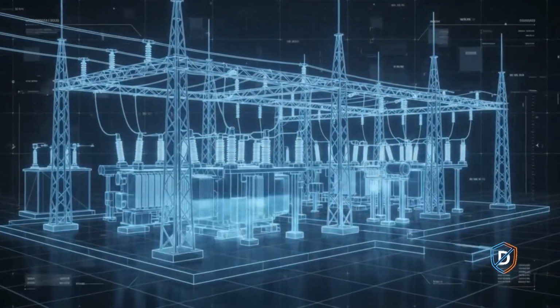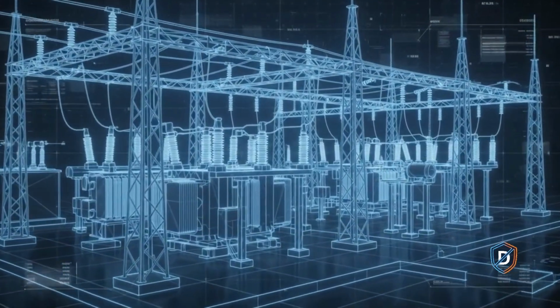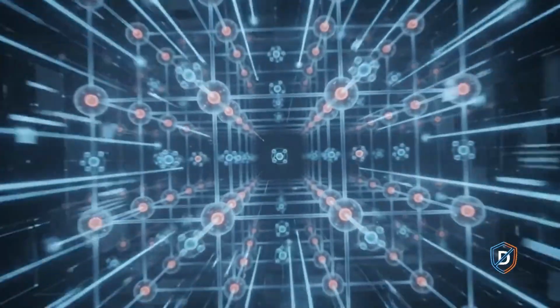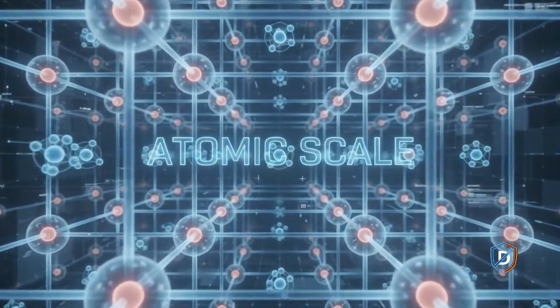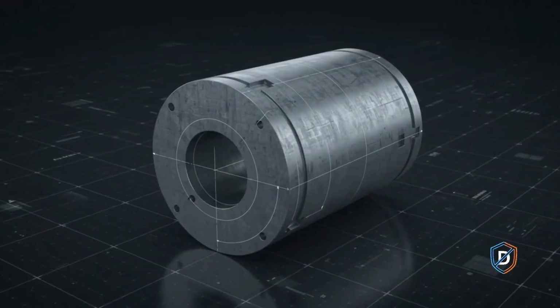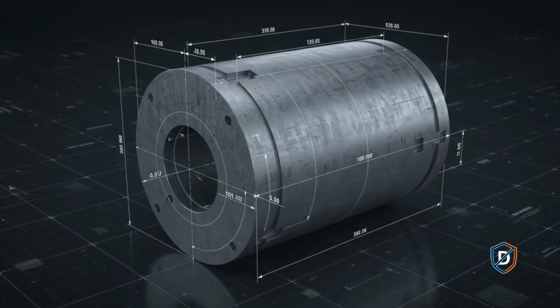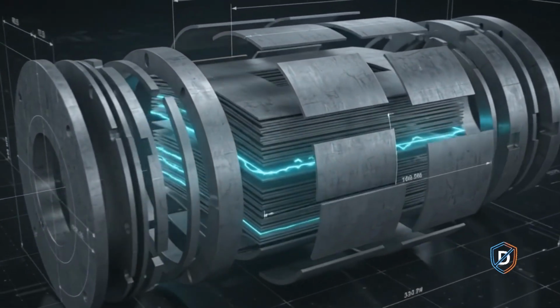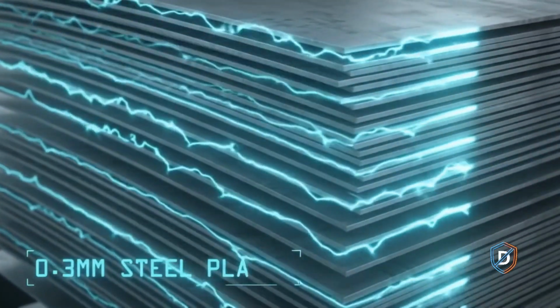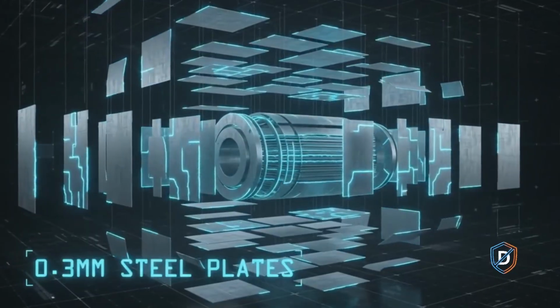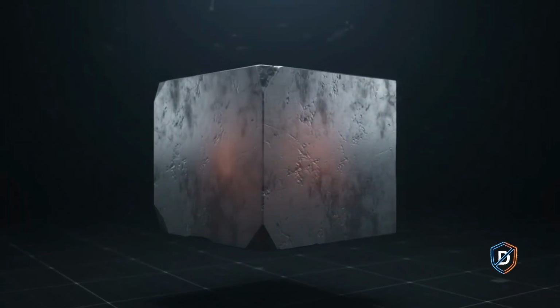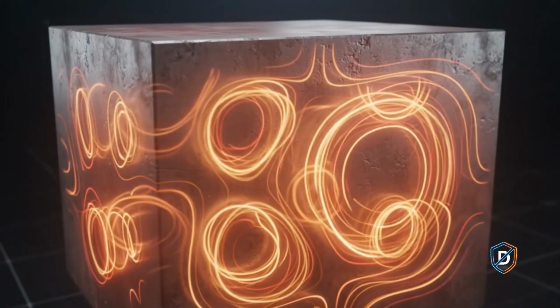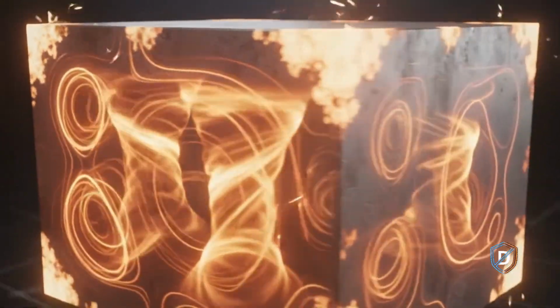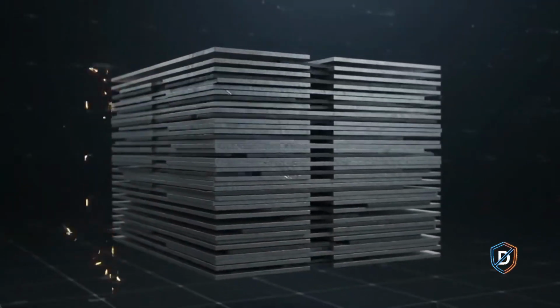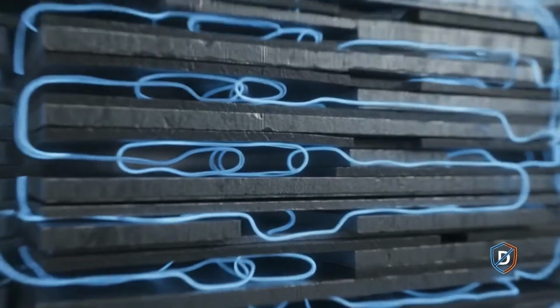To understand why these massive machines are failing, we have to zoom down to the atomic structure of silicon steel. To stop stray electrical current from jumping sideways, a 400-ton core isn't solid iron, it's built from thousands of microscopic steel sheets. Without this laminated design, internal swirl currents, called eddy currents, would bake the iron core solid in seconds.